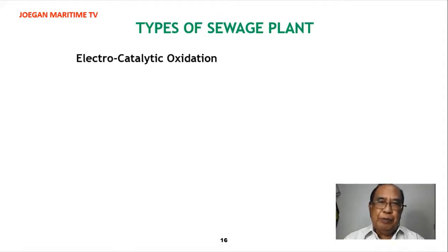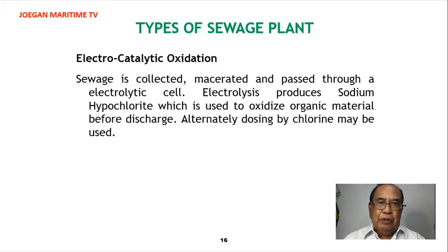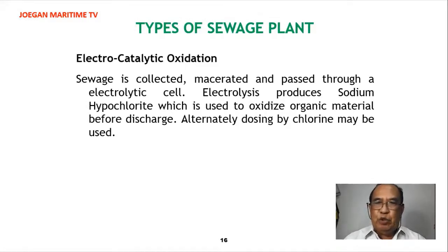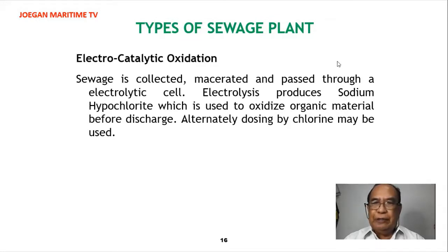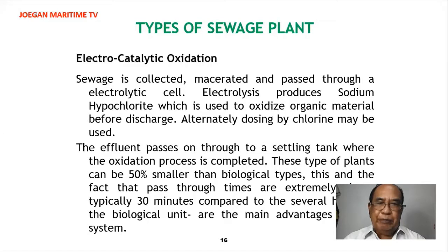Another type of sewage plant is the electro-catalytic oxidation plant. Sewage is collected, macerated, and passed through an electrolytic cell. Electrolysis produces sodium hypochlorite, which is used to oxidize organic material before discharge. Alternatively, dosing by chlorine may be used. The effluent then passes through a settling tank where the oxidation process is completed.